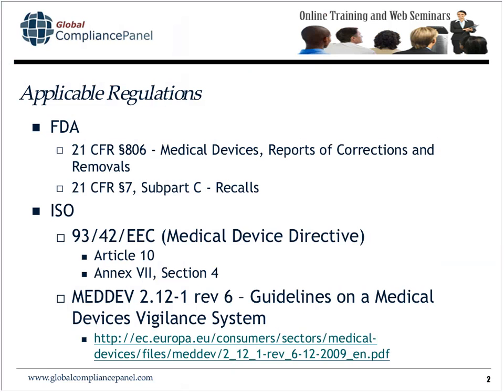From an FDA perspective, Section 806 is actually titled Medical Devices, Reports of Corrections and Removals, and Section 7 is recalls. From an ISO perspective, the Medical Device Directive itself addresses these types of market situations in Article 10 and also in Annex 7, Section 4. And there's a guidance document, 2.12-1, the current Rev is Rev 6, and it's titled Guidelines on a Medical Devices Vigilance System. Vigilance is the European Community's definition of what to do, how to handle it when you receive feedback from the field that is negative, that requires you to either correct or get back the product.